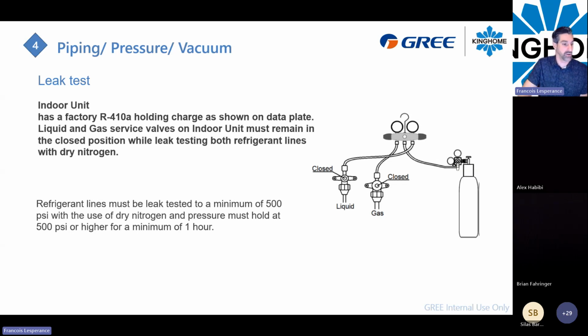By connecting your gauges and your hose on the valve, just remember that you will have to push pressure inside the suction line and inside the liquid line. It's not connected in any way with the coil because all valves are closed at this point. So you will have to make a separate pressure test and a separate vacuum for your suction line and for your liquid line. Make sure you hook your two hoses on the gauge and you make two different tests, one for each line.